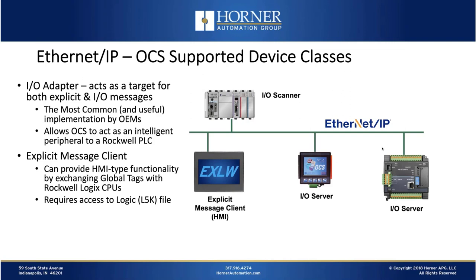The most common application is the OCS or RCC acting as an I/O adapter, meaning our product can exchange data at high speed with an I/O scanner like a Rockwell Logix CPU. That's the application OEMs using Horner products need most often. For example, an OEM that utilizes the Horner XL4 all-in-one controller to run an industrial oven — some customers who buy that oven want to interface with Rockwell-based systems already in their plant. The Horner controller offers Rockwell connectivity without the Rockwell price premium. The XL4 is set up to act as an I/O adapter through Ethernet IP, configured to share critical process parameters, status, and alarm data available to the plant systems over Ethernet IP.